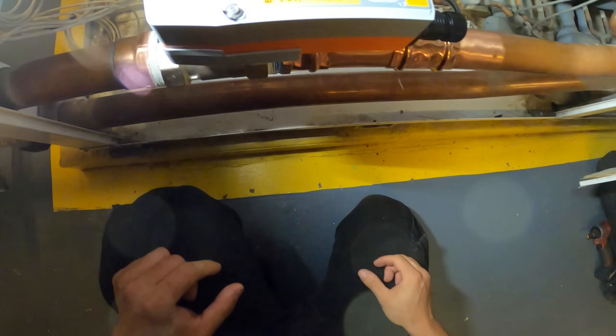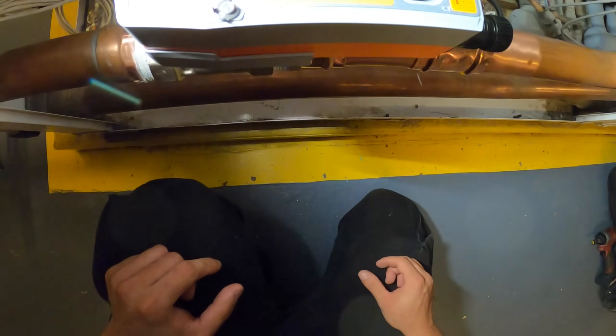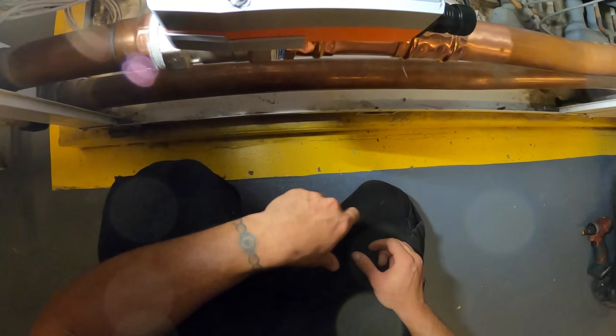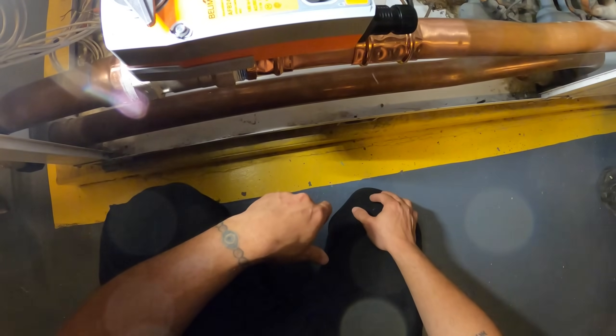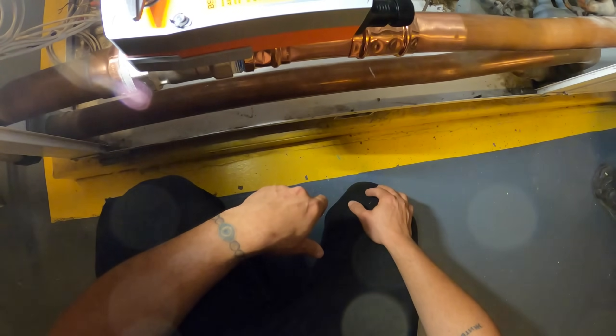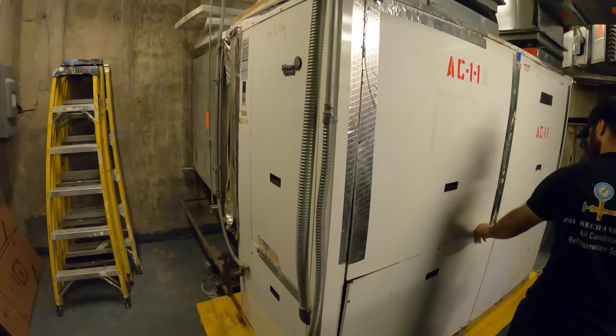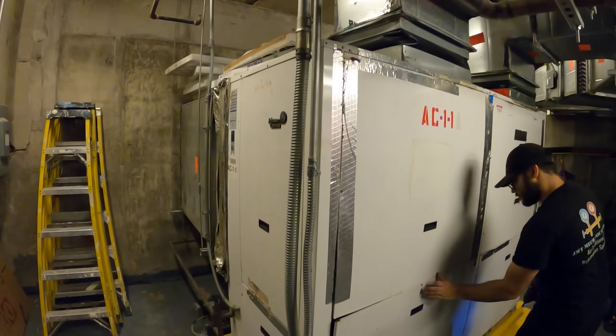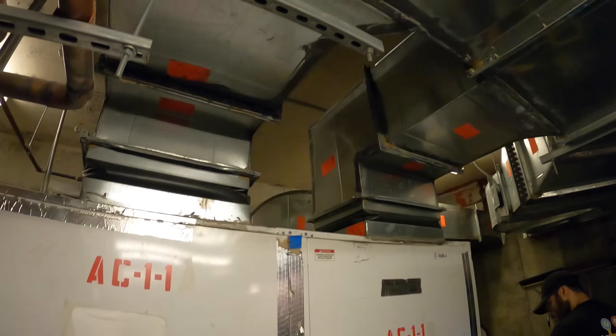I'm going to unlock it — right there, it's going back, it's closing. We're going to have to come back because the building is controlled by BMS — Building Management Systems. For some reason the heat is coming on with the cooling so the valve doesn't open. We'll be back with that company and work together to get the settings right. If anyone found this video interesting or helpful, please drop a like, comment, and subscribe as I come out with new videos every week. I'll catch you all next time.